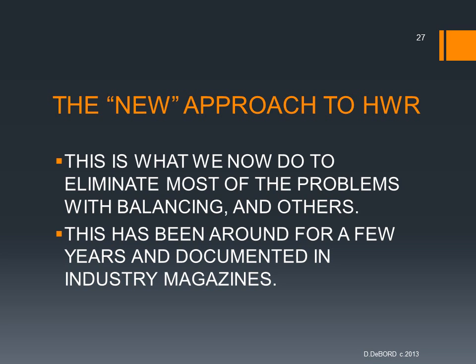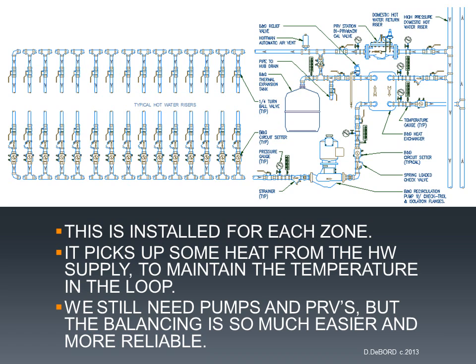What I like to call a new approach to hot water return has been around for a few years, but it's what we do now to eliminate most of the problems with balancing and some other problems. Like I said, it's been around for a few years. It's been documented in magazine articles. I'm sure you've seen something somewhere in PS&D or our new Plumbing Engineer magazine. Here's what it looks like. It's also called the zone system.